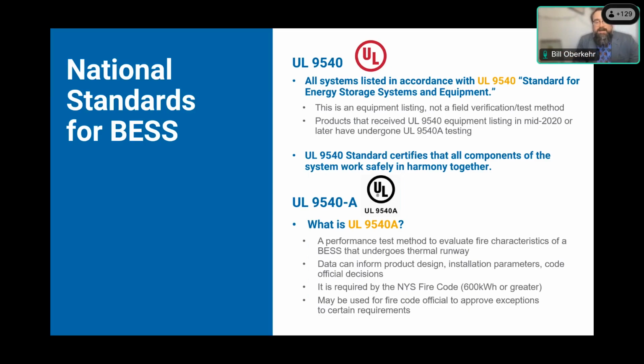The UL 9540A test is not binary. It is a test method, not a pass-fail test. The UL 9540A test involves initiating thermal runaway in the system and then recording how that system behaves once thermal runaway has been induced. So this is basically a hazard mitigation measure. In order to know how we need to site these projects and what sort of separation distances we need, we induce thermal runaway. We create the situation we're most worried about and see what it does, then base our decisions on that lab data instead of making even educated guesses about what the case should be.